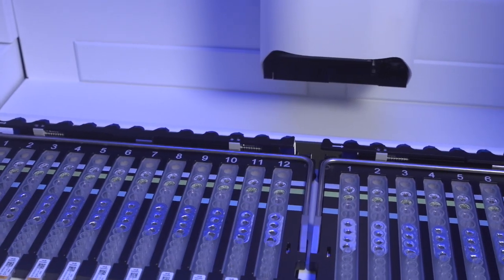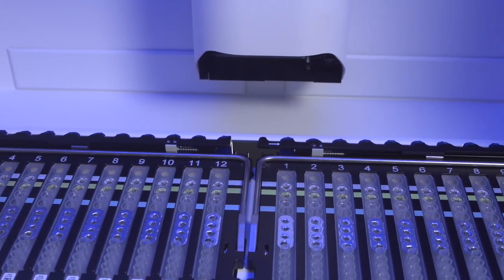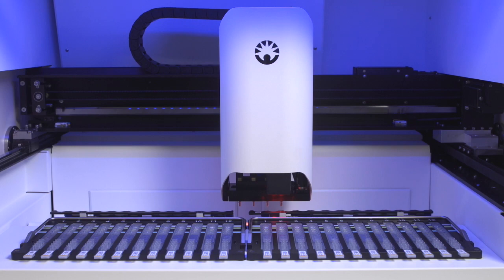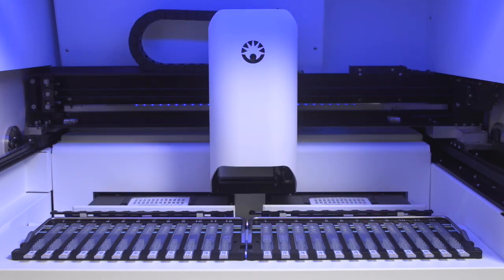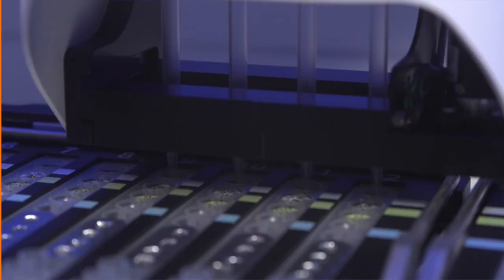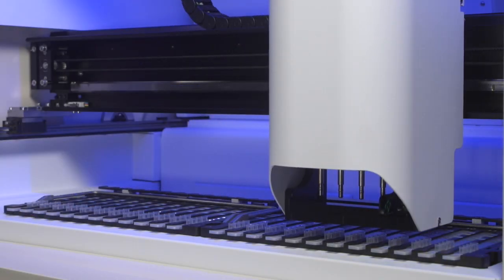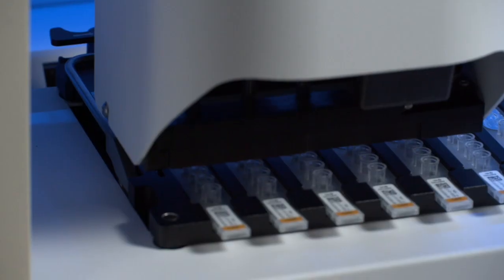The sample racks are placed on either side of the interior. The centerpiece is the robotic head, the workhorse of the BD Max system. When at rest, the robotic arm sits at the middle rear of the instrument interior. The robotic head uses a pipette head to transfer fluids. The barcode reader attached to the pipette head reads sample and reagent barcodes during operations.